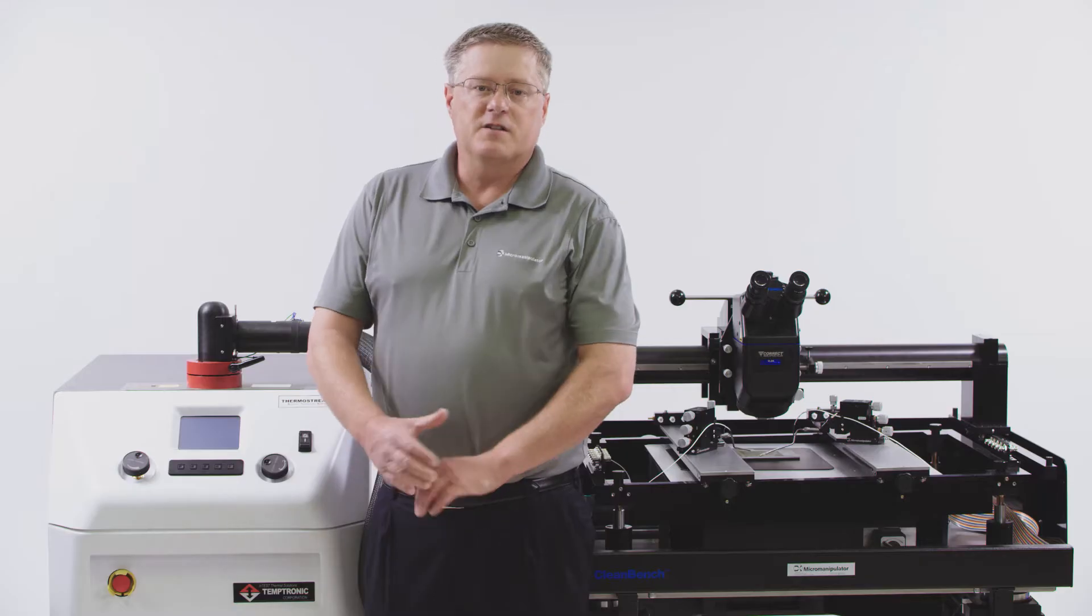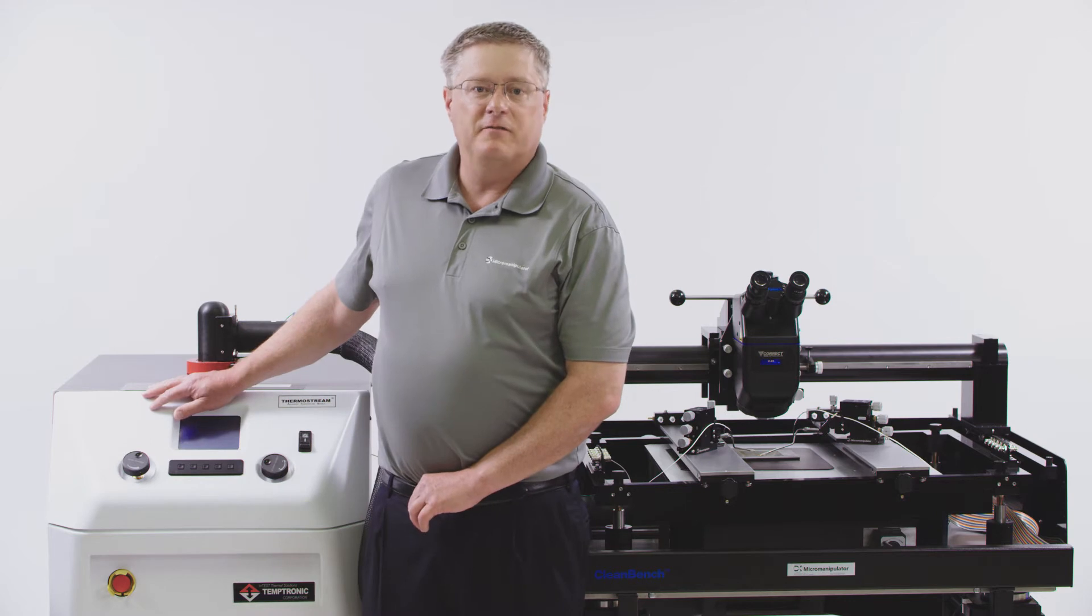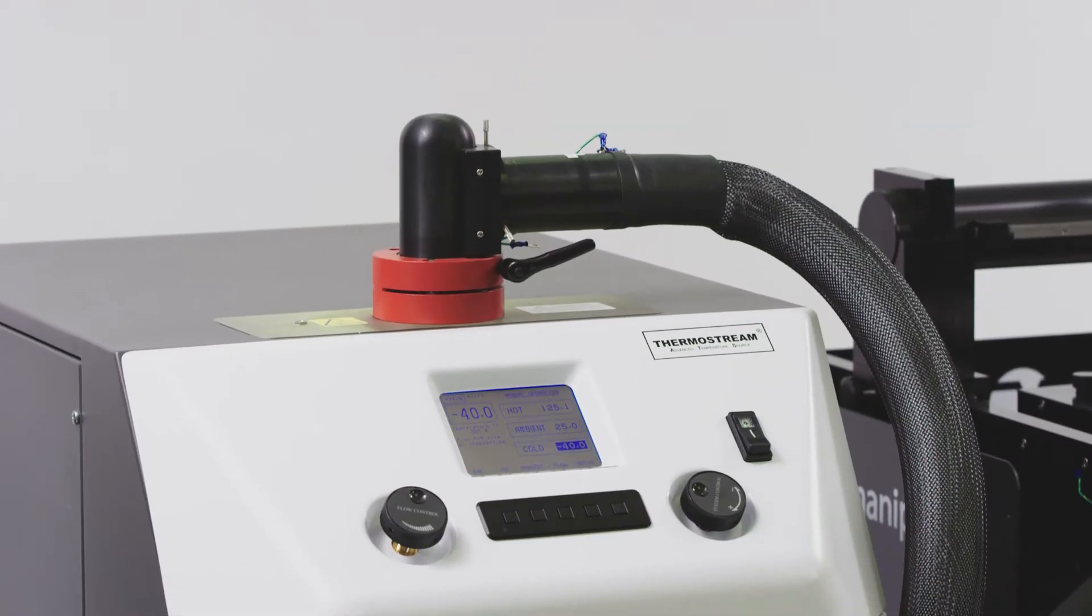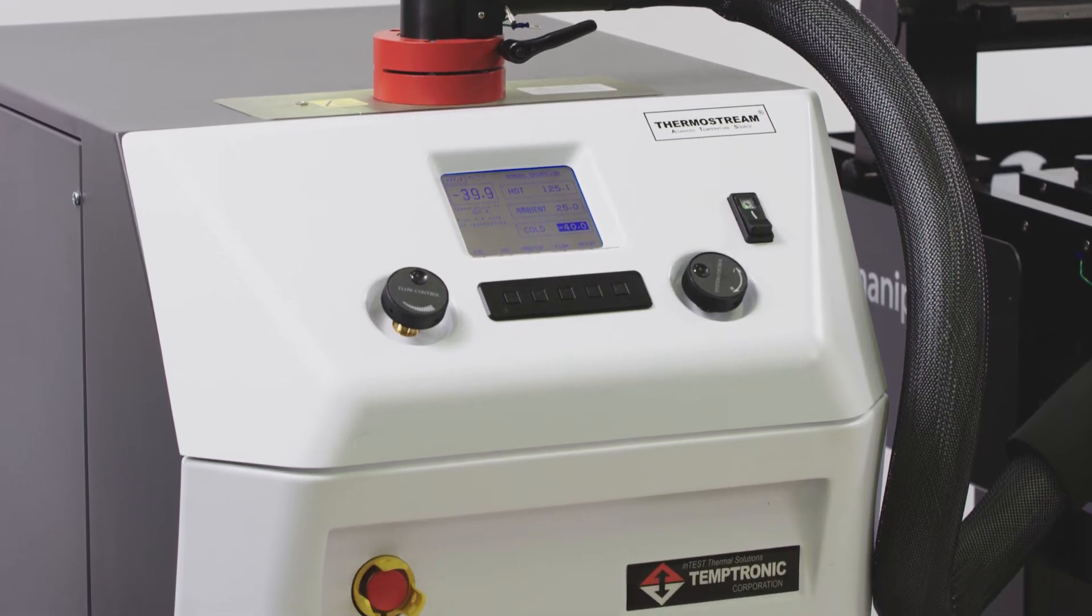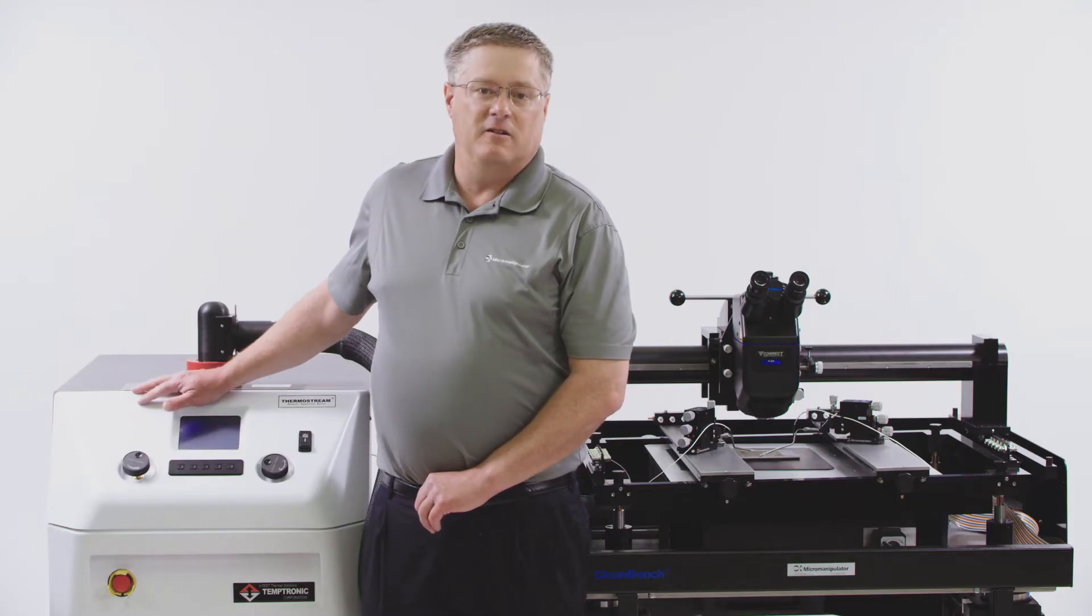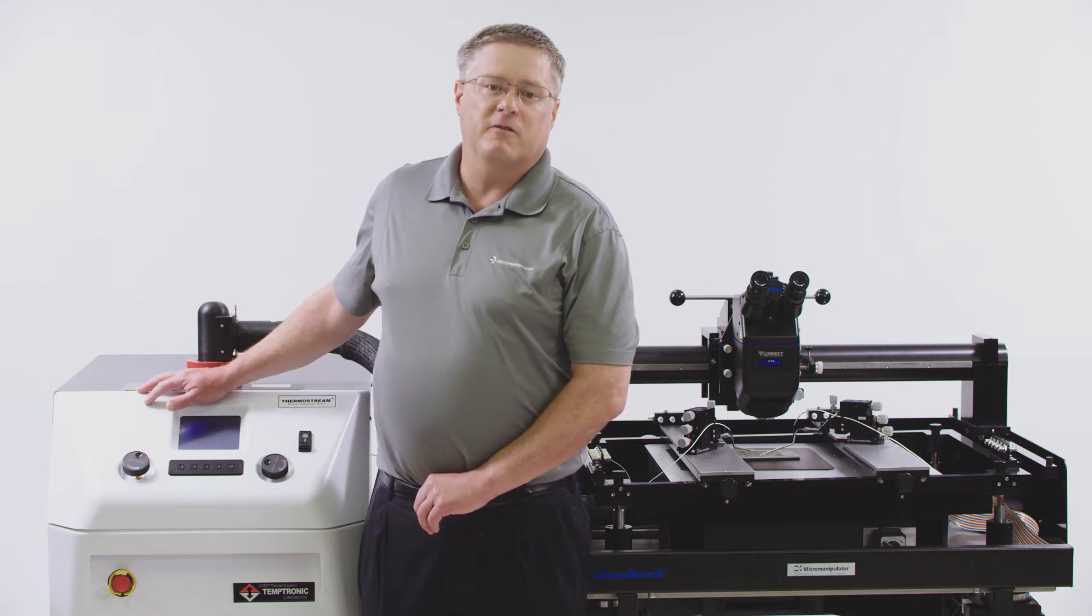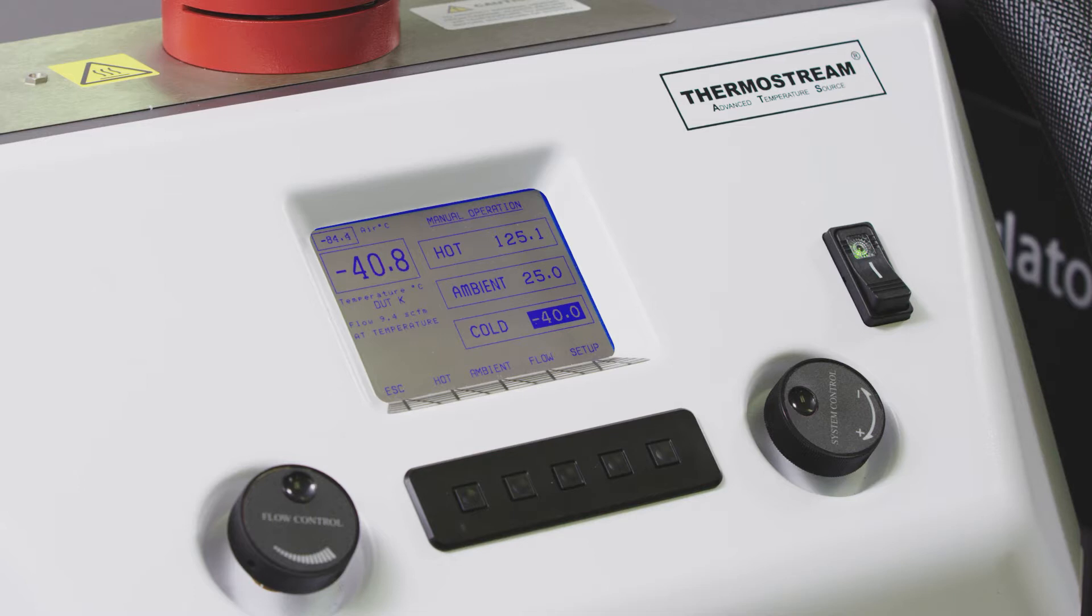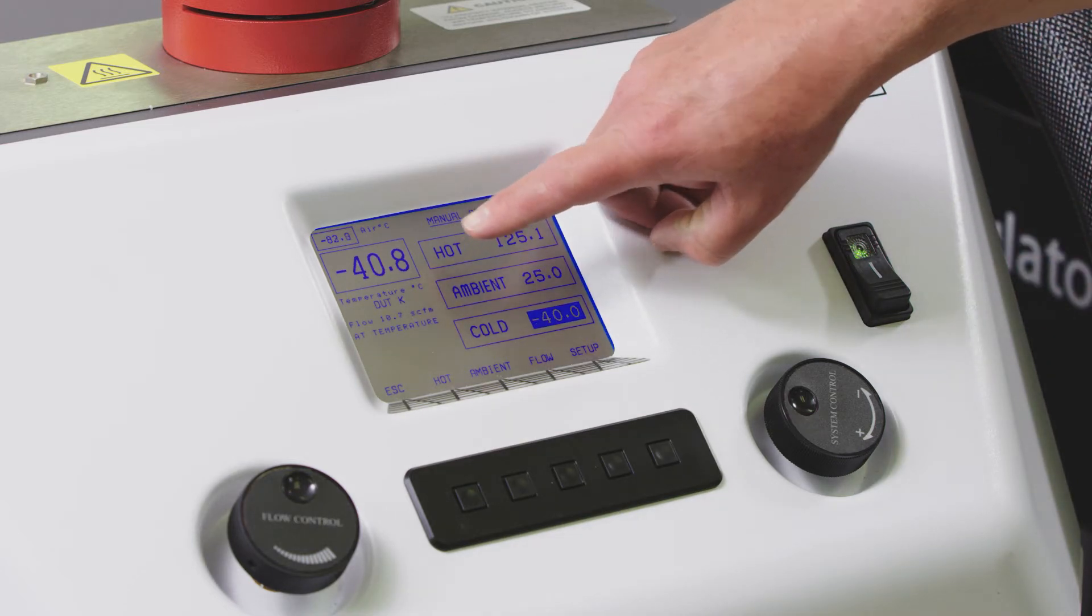Versas that are configured for temperature testing use industry standard off-the-shelf thermal forcing units. These units allow Versa to heat and cool your part frost free so that you could easily probe them. You probably already have these devices in your lab now to adapt them to your own Versa, but if you don't you can also buy them from Micromanipulator. As you can see by the display on the thermal forcing unit, the temperature of the chamber is currently at minus 40C and there is no frost inside the chamber.